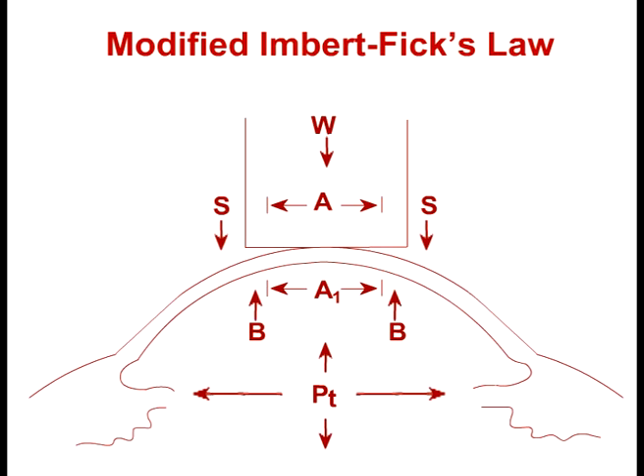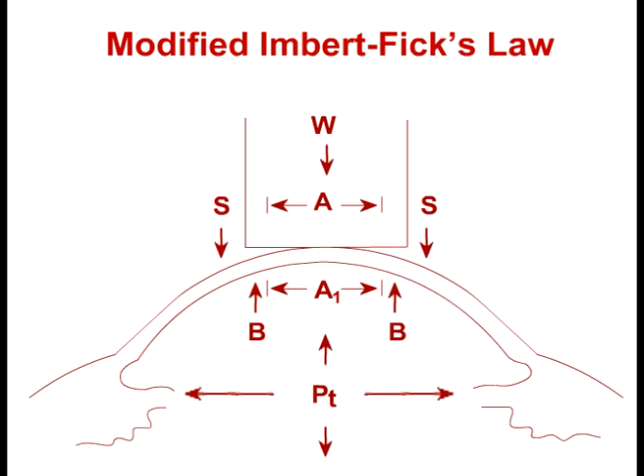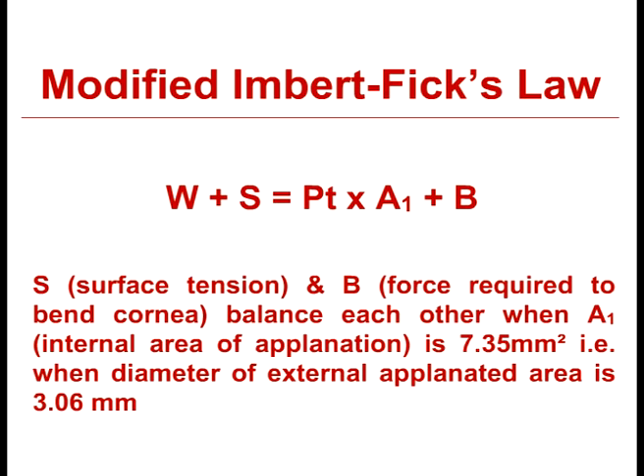Since the eye is neither a perfect sphere nor is thin, dry, or flexible, some other forces come into play and thus the law needs modification. Volume displacement and ocular rigidity are negligible in aplanation tonometry. The surface tension of tears and the force required to bend the cornea balance out each other when the diameter of external area of aplanation is 3.06 mm.